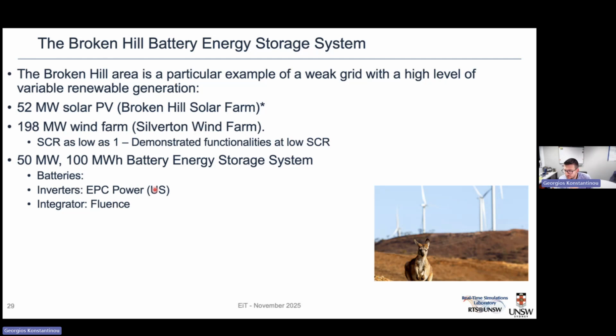Geography out of the way, electrically we have to deal with that very long remote transmission line, a 52 megawatt solar PV system, a 200 megawatt wind farm based on type 3 double fed induction generator wind turbines, and now the inclusion of this 50 megawatt battery that we need to get into a specific control self-synchronization manner that will allow us to maintain system stability in that particular area.